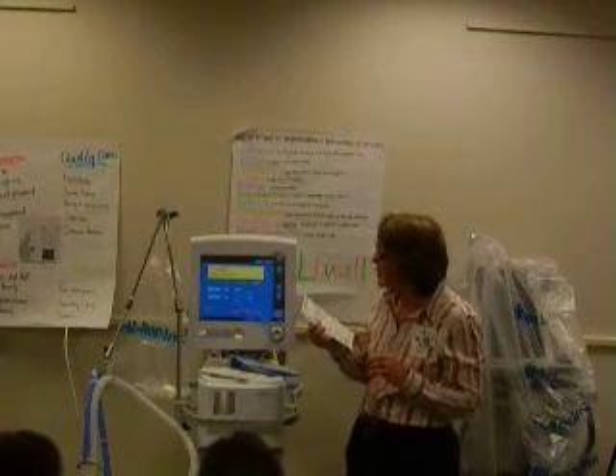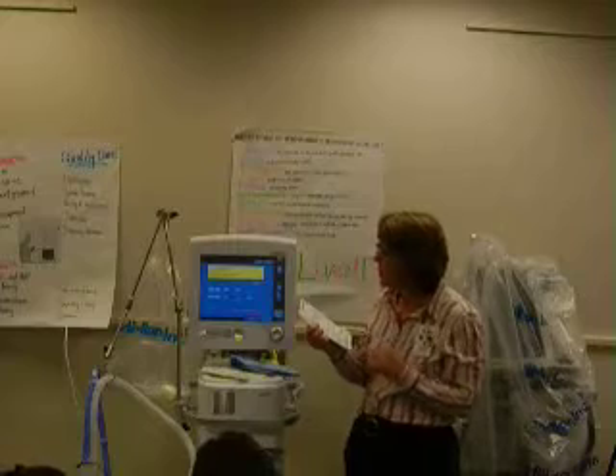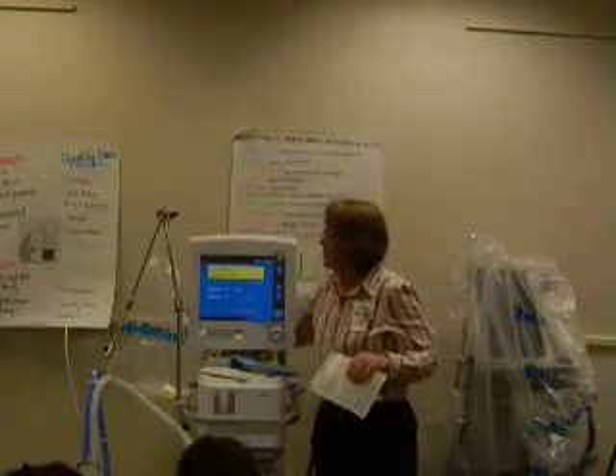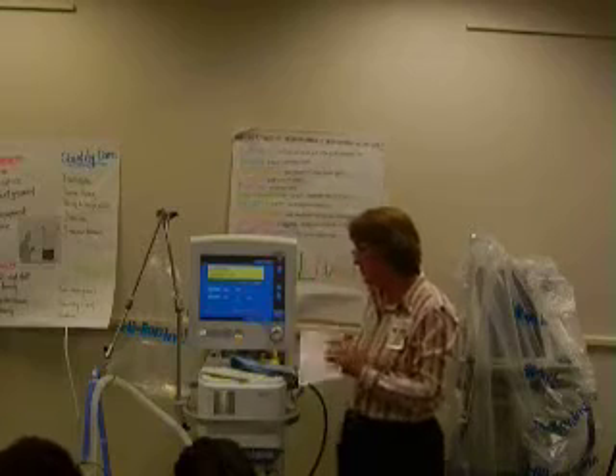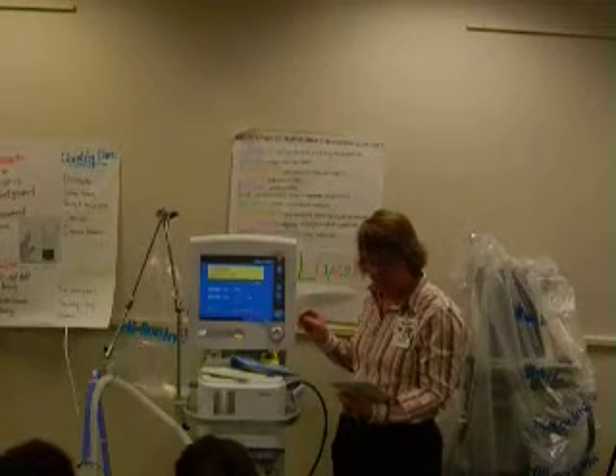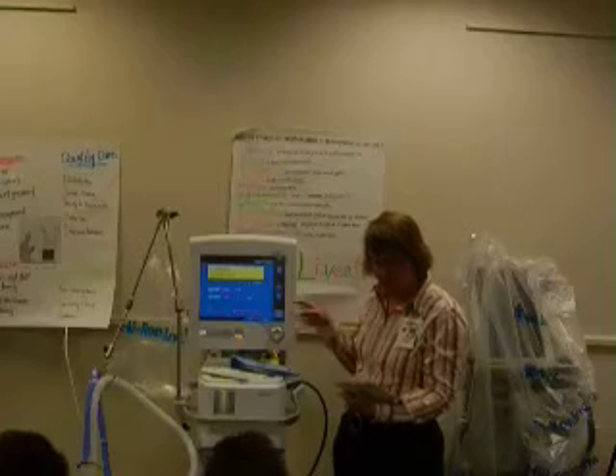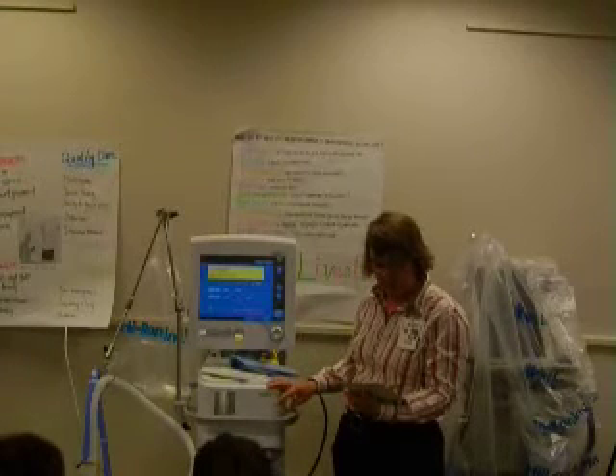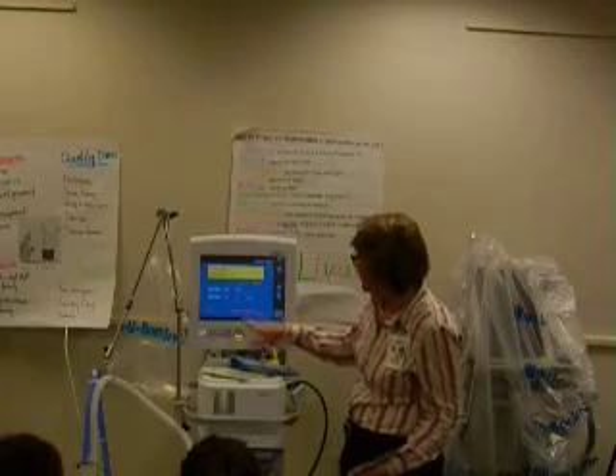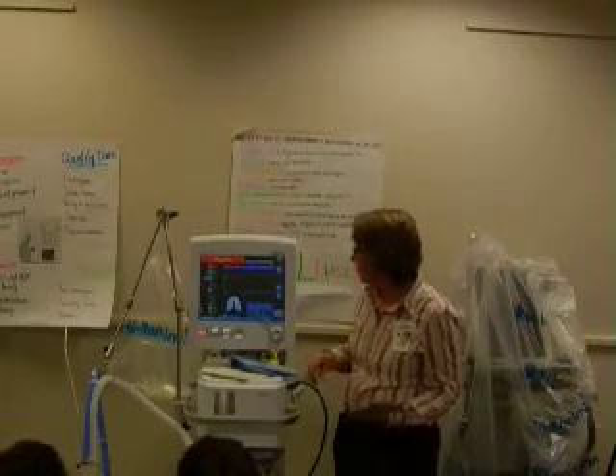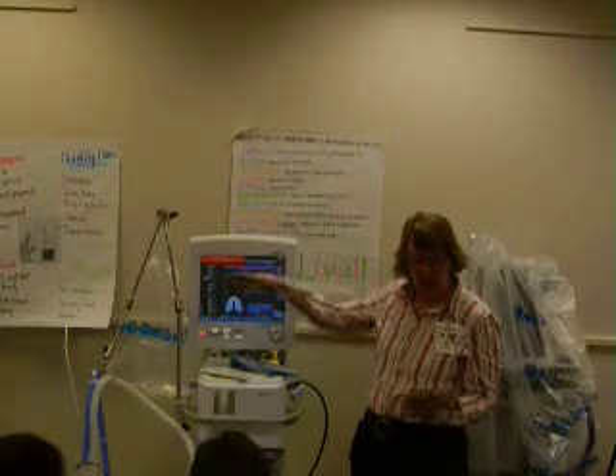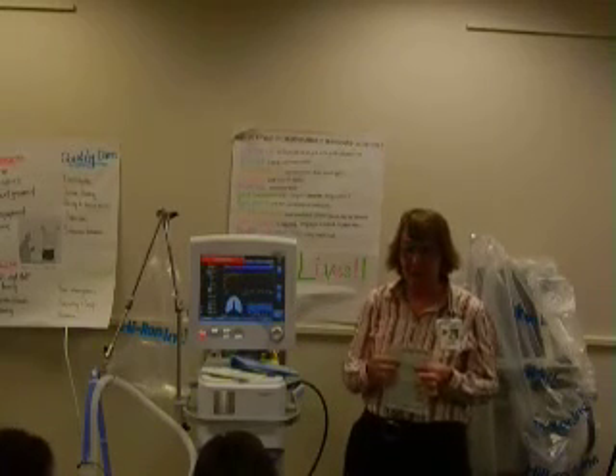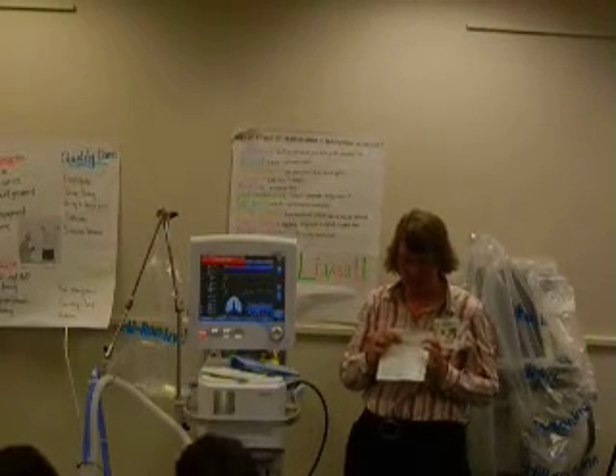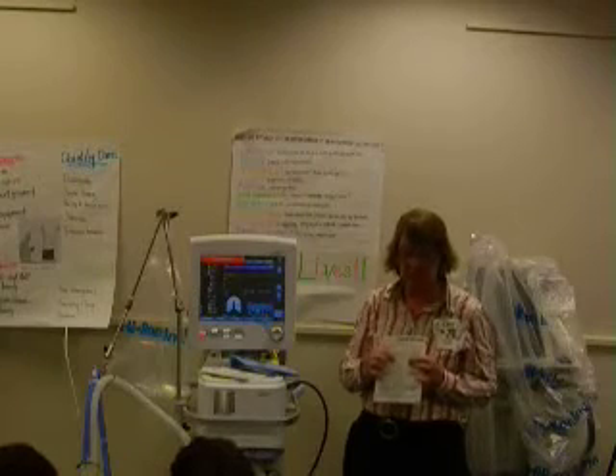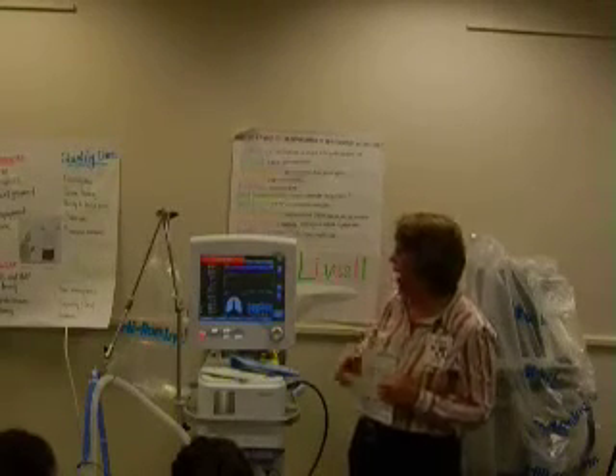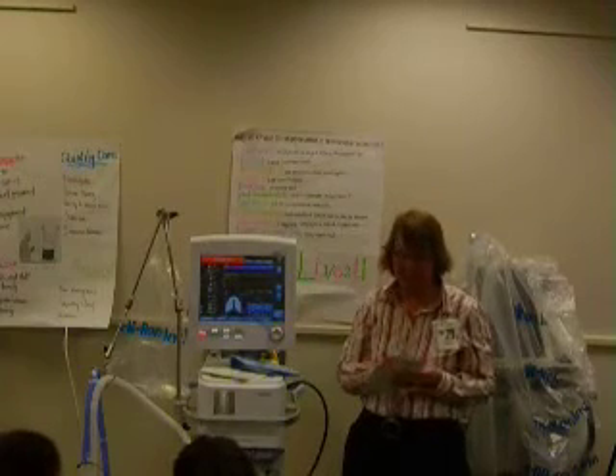First step is connect the ventilator to AC power and compressed air supply only, not oxygen. We're going to unhook our O2, and set the ventilator up for normal ventilation. Switch on power, we already did that. From the patient setup standby window, select new patient and then hit start. The first thing you're going to see is oxygen supply failed. That's what it says here, verify. Oxygen supply failed, that's what you want to see. Then after a few minutes, you'll see low oxygen in the message bar. I'm not kidding, it takes a few minutes for the low oxygen message to come up on the screen.